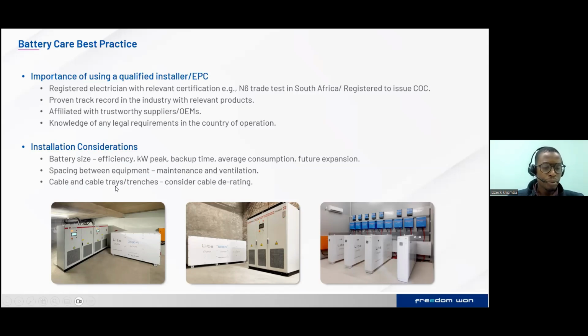Very important as well is to look at the cable trunking system that's got to be utilized. In this section, we need to consider cable derating, because depending on the type of trenching system or cable trunking system that you use, it affects your cable rating. So these are things we need to take into consideration when looking at battery installation. The temperature rise in a specific trunking system varies, and according to the SANS standards, it requires us to derate based on the trunking system used. So it's very important.